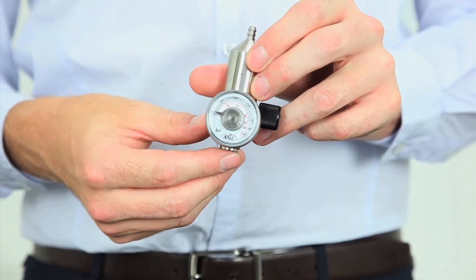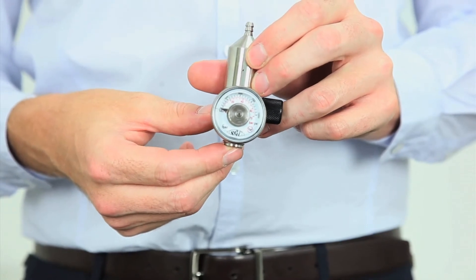Please note this regulator is not to be left attached to the cylinder when not in use due to potential leakage. For more information please subscribe to the CAC Gas Blog at the link below to help keep you up to date with the top tips to maximise the efficiency of your calibration gas program.